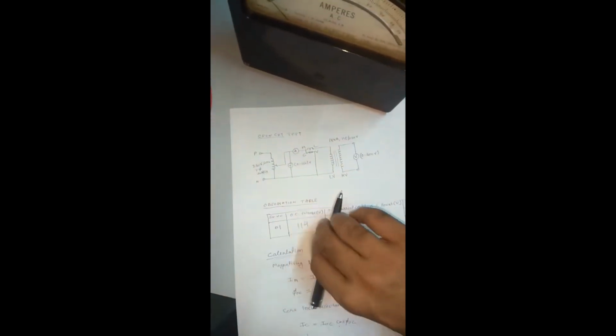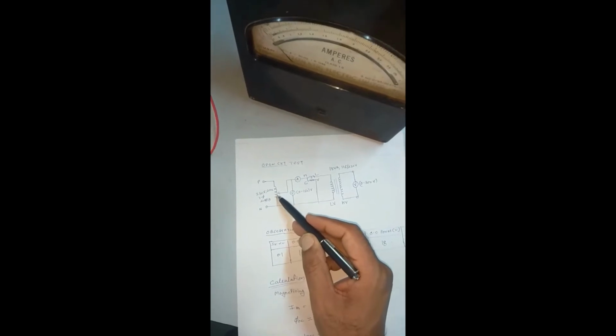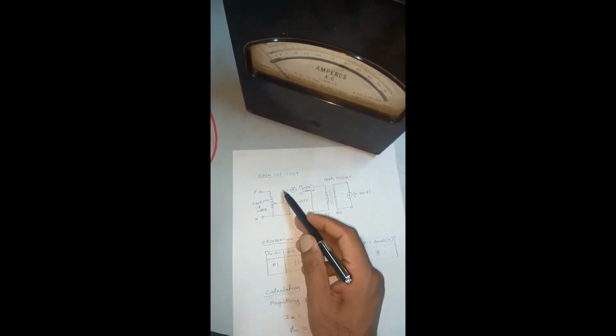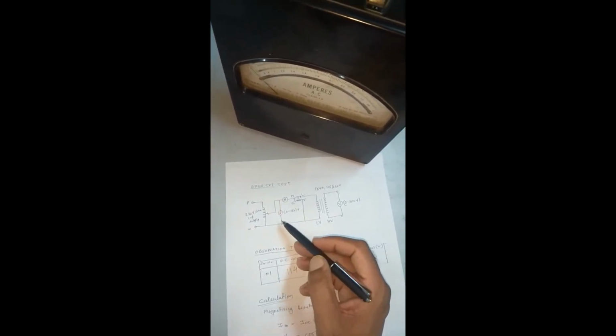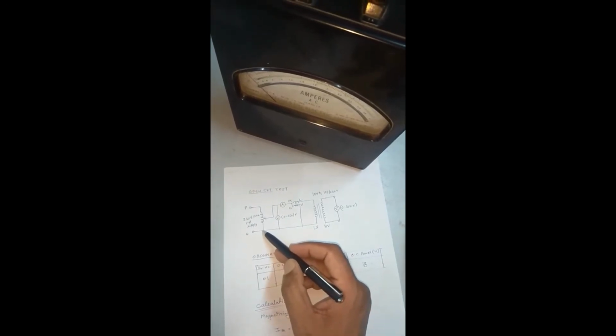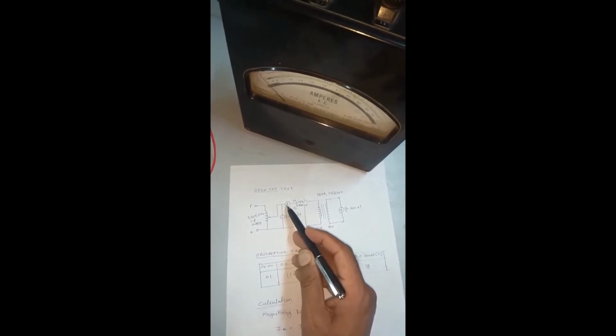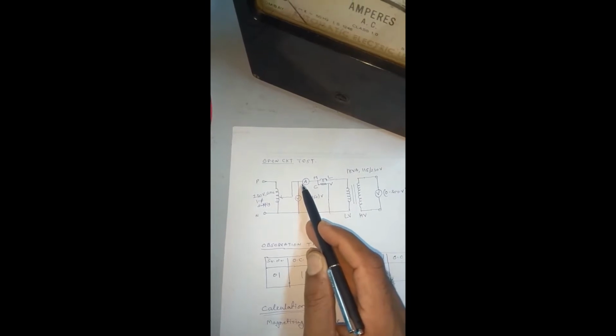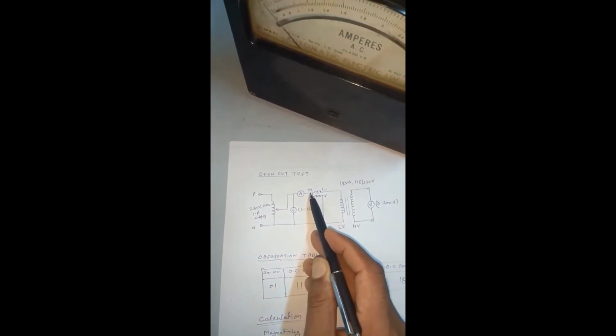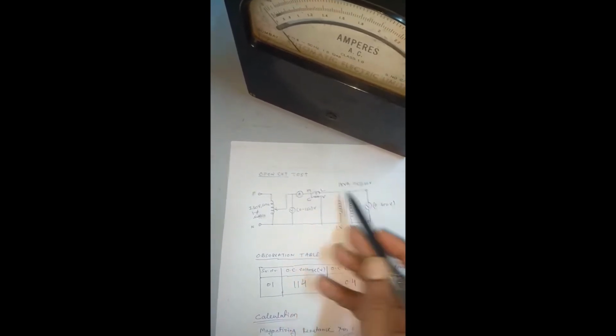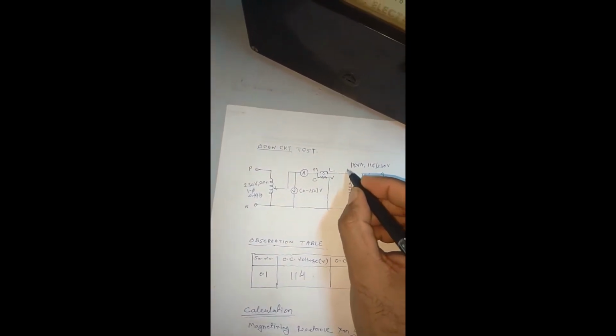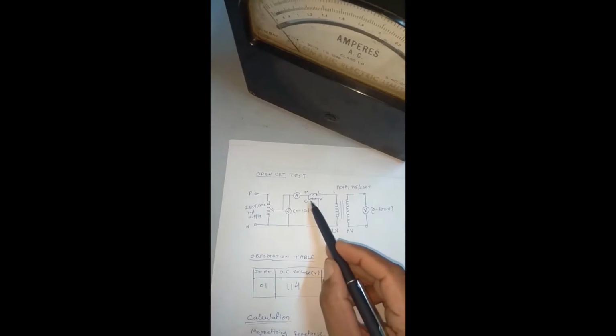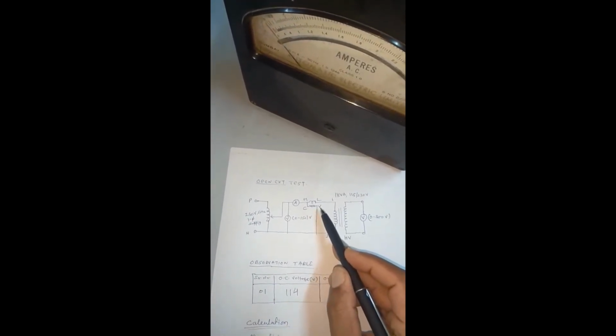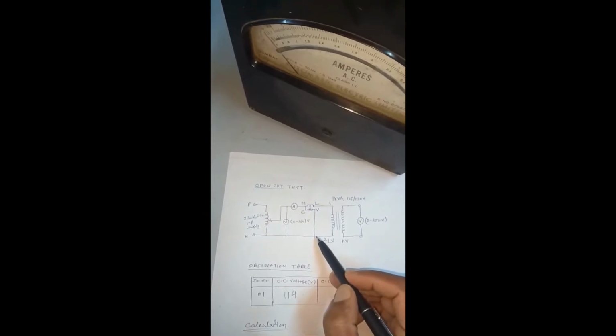So let's see the connection diagram for the open circuit test. There is a supply that is given to the dimmerstat. From here the 2 terminals are coming. One terminal is connected to one terminal of the voltmeter, and the other terminal of the voltmeter is connected to the second terminal of the dimmerstat. Then from here one terminal is connected to the common terminal of the ammeter, and the other terminal of the ammeter is given to the main of the wattmeter. Then the terminal L is connected to one terminal of LV. Let us mark it as terminal 1. The V terminal is connected to the other terminal of LV.